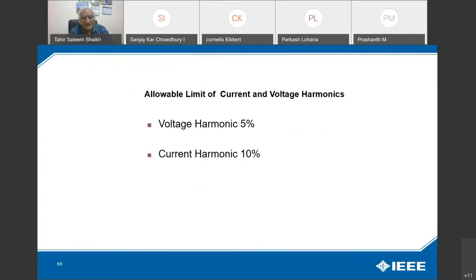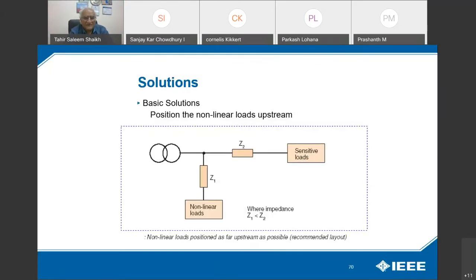In general practice, many global multinational companies have set allowable limits for voltage and current. Voltage harmonics of 5% and current harmonics of 10% is the maximum limit. Otherwise, we have to go for other solutions. So these are some of the basic solutions. The basic solution is to position the non-linear loads upstream, close to the source. This figure shows Z1, the impedance for non-linear loads, and Z2, the sensitive loads, so we have to place them accordingly. You have to decide with the harmonic spectrum which solution is best for you and how much to invest in this. That is your own decision.